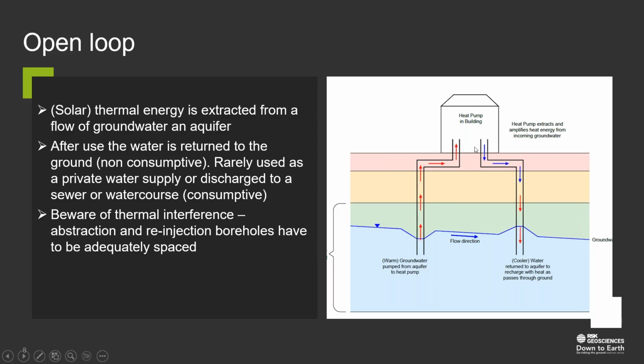If you re-inject it this way, that's called a non-consumptive scheme, which is relatively easy - the Environment Agency will accept it in most situations because you're not taking groundwater from the aquifer. But using it in a consumptive manner, for example taking the water out and using it for drinking water in an isolated building, is more difficult in areas where groundwater is scarce. One thing to watch with open loop schemes is avoiding thermal interference between your abstraction and reinjection boreholes, so they must be spaced properly - I'll talk more about that in the next slide.